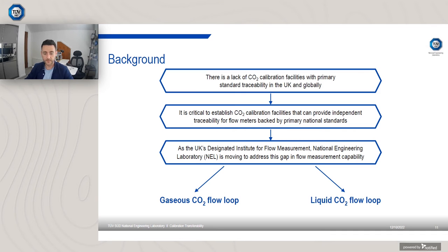As the CCUS schemes become more widespread and the carbon price increases, there's potential that the measurement uncertainty for CO2 will decrease, and as such, even although you potentially could calibrate in one fluid and use it with CO2, to get the required low measurement uncertainty, you would ideally want to calibrate in CO2. So there still potentially will be a requirement for a gas CO2 flow loop and a liquid CO2 flow loop, irrespective of whether you can calibrate in one fluid and operate in another.